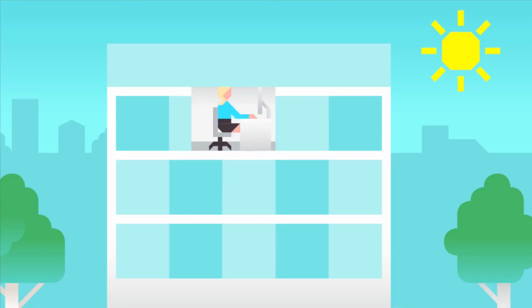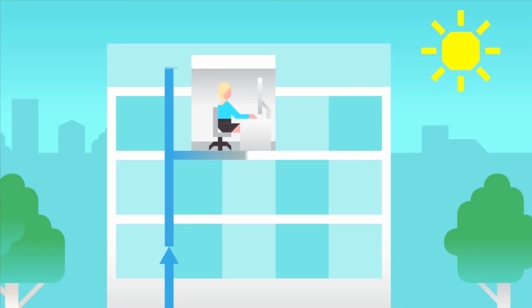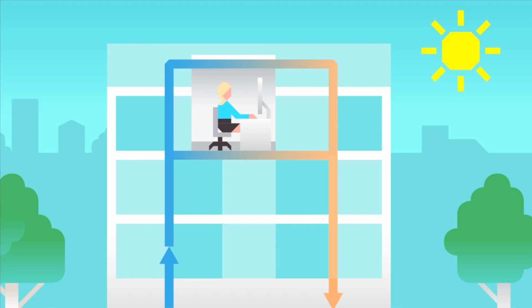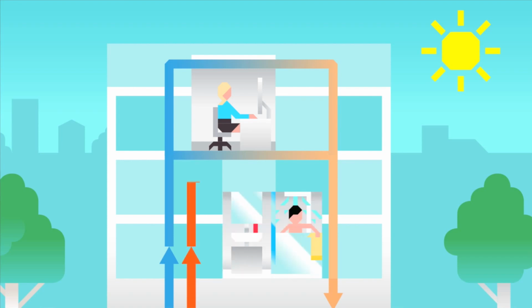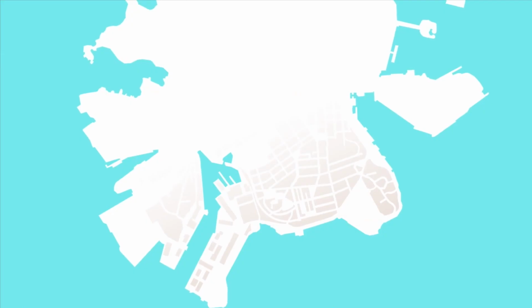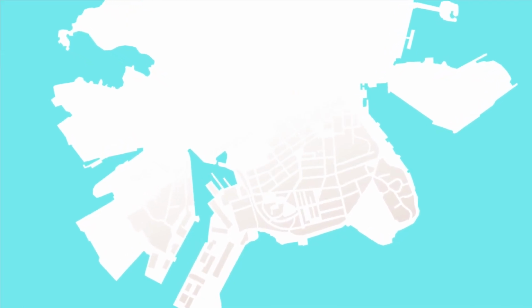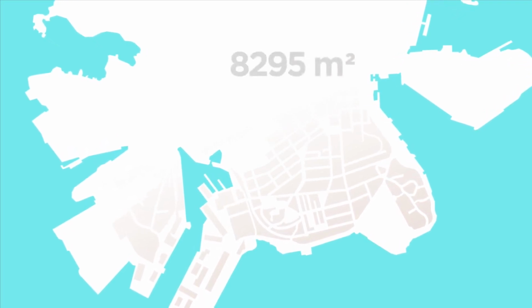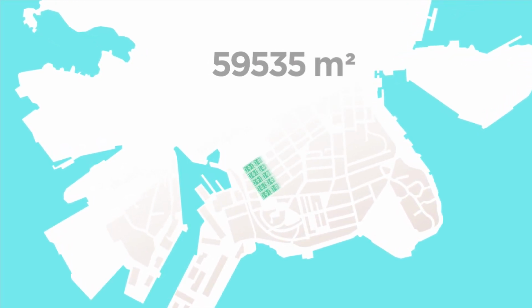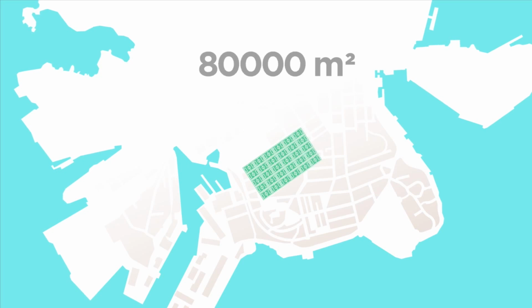The plant also uses cooling to collect solar heat. The smart energy system at the Katri Vala plant combines the energy flows of heating and cooling. Buildings are used as energy sources when they're warmed up by the sunlight in the summer. Cooling is used for recovering surplus solar energy from buildings to be processed further at the heat pump plant. The system produces plenty of solar energy for the use of residents in Helsinki. In order to produce a similar amount of energy with solar collectors, you would need as much space as 30 football fields. That kind of space is not easily available in a densely built urban structure.